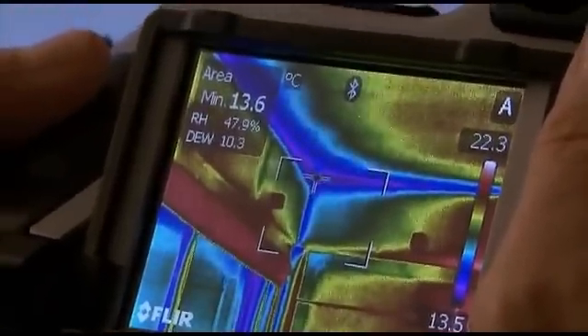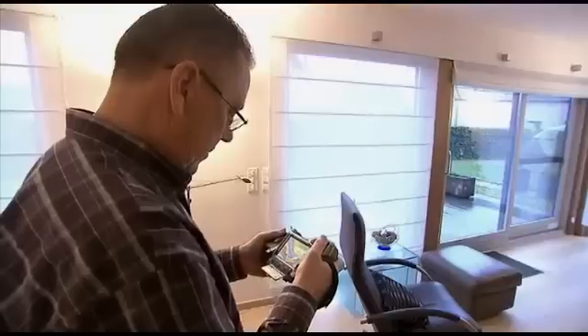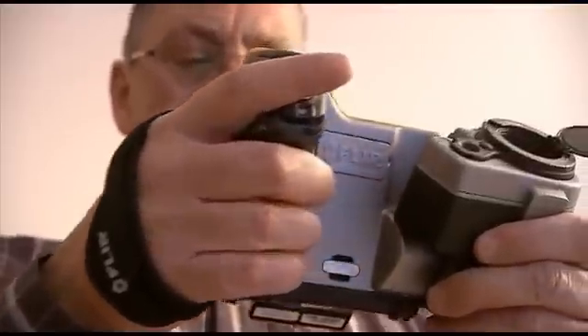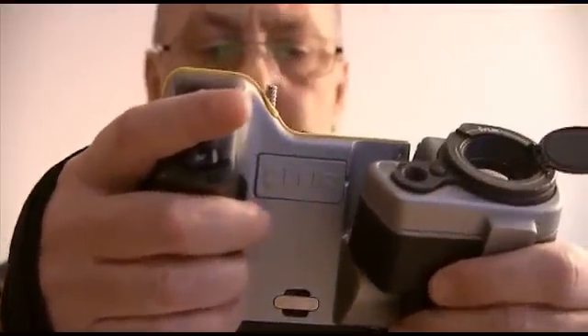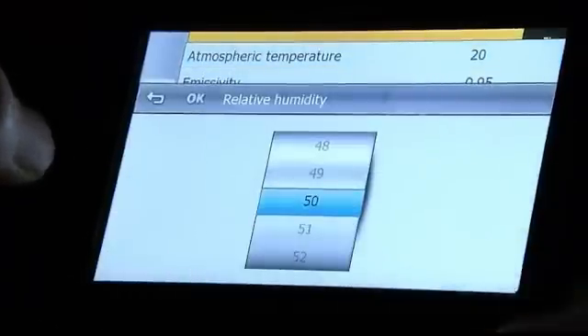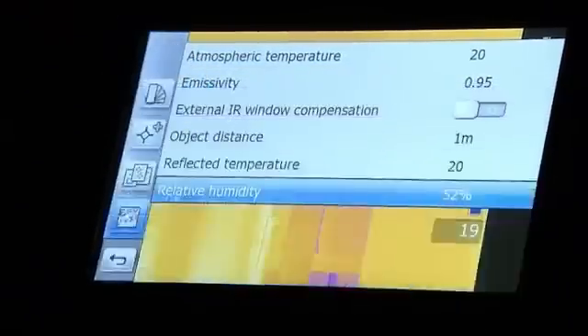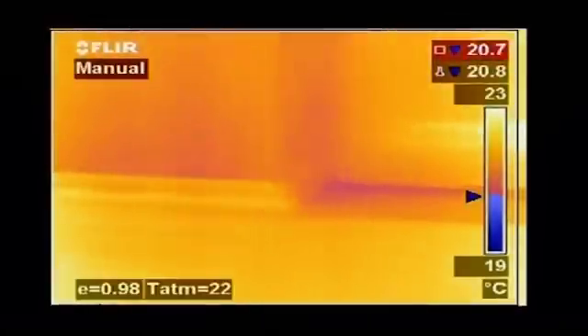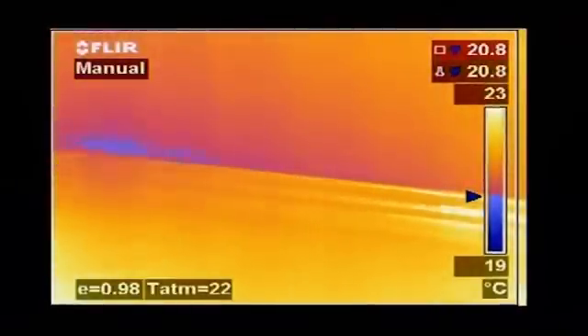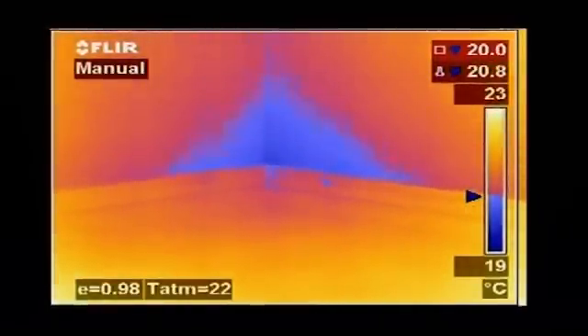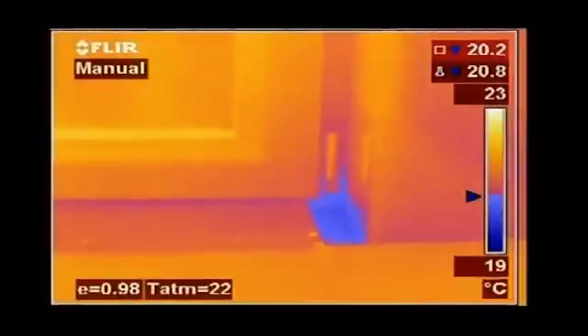If you don't have an Extech moisture meter to hand, all parameters used to identify potential condensation areas — such as relative humidity and temperature — can be set directly in the camera. The FLIR thermal imaging camera will calculate the dew point. Thermal imaging cameras with dew point visualization software can highlight endangered locations automatically and provide a colour alarm in the image.